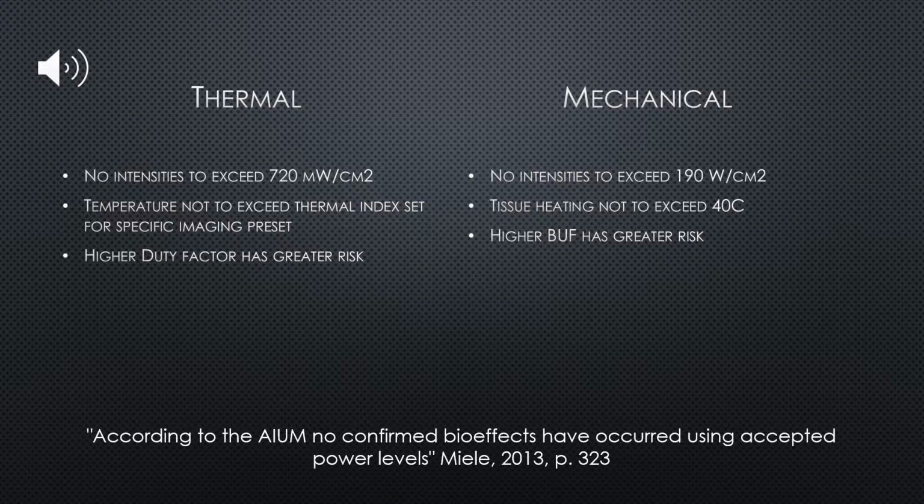So, some safety guidelines for bioeffects. For thermal, no intensities should exceed 720 milliwatts per centimeter squared. The temperature should not exceed the thermal index set for specific imaging presets. And a higher duty factor has a greater risk of causing bioeffects. The duty factor is pulse duration divided by the pulse repetition period, which is the percentage of time sound waves are transmitting from the source. So the longer you have the sound waves transmitting, the higher risk you have for having thermal bioeffects.